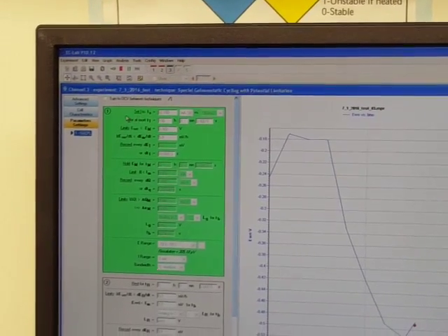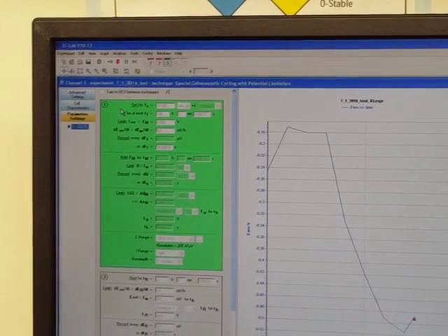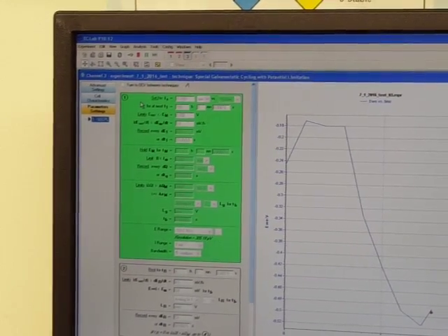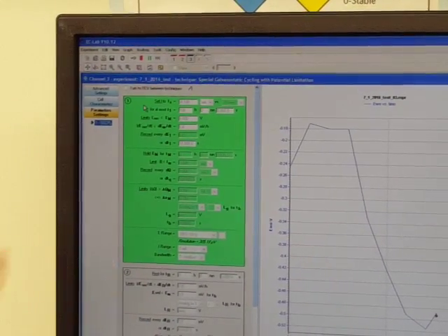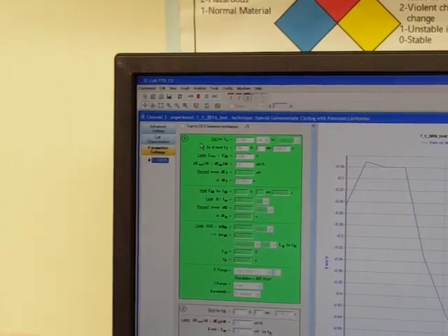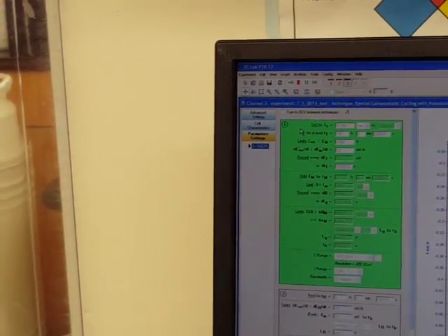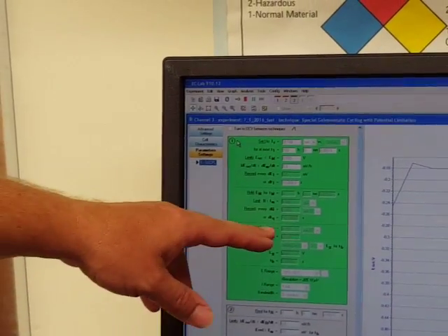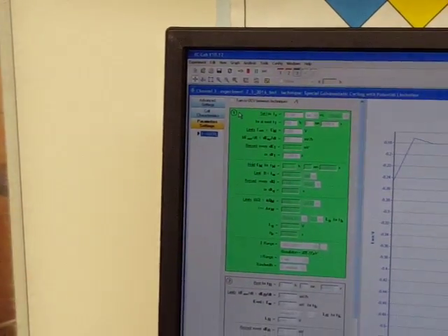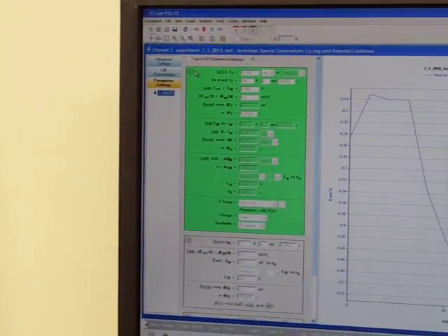So minus 0.1 means it's going to try to pull 0.1 milliamps from our cell, okay? And then as it pulls 0.1 milliamps, the voltage will adjust depending on how much voltage can still remain as that much power is being drawn. As the voltage adjusts and stabilizes, it'll be monitoring the derivative, the slope of that line. And as soon as it becomes flat, according to our parameters that we have set here, then it will shift to the next sequence, okay?